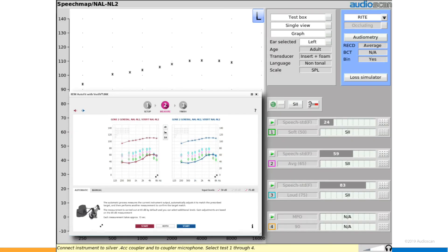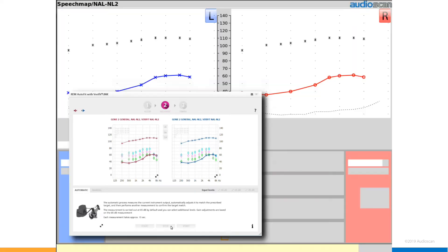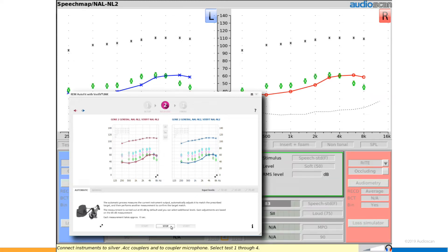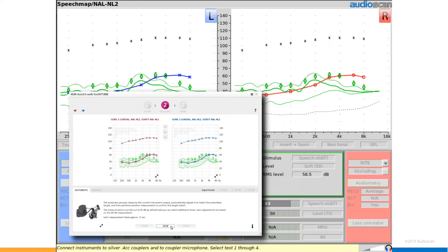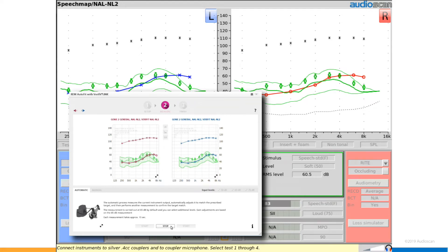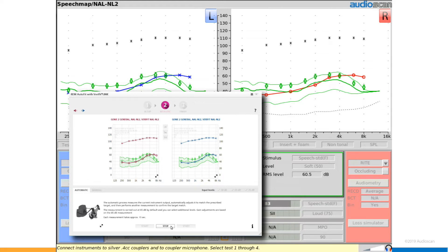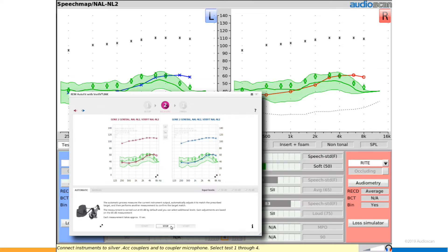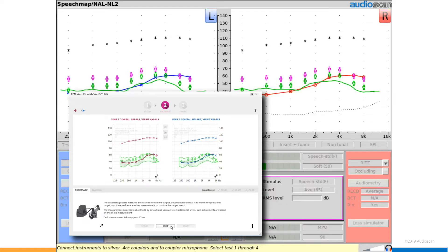We have exciting news for users of our VerifitLink automated fit-to-target tool. With this release, the Verifit2 now supports simultaneous binaural measurements through VerifitLink, both in the test box and real ear. VerifitLink has already shown to substantially cut down the time needed to verify hearing instrument fittings. Having the automated sequence test binaurally will decrease that time even more. This will be implemented first in Oticon's Genie 2 release for 2019.2, expected in the market around the end of August.